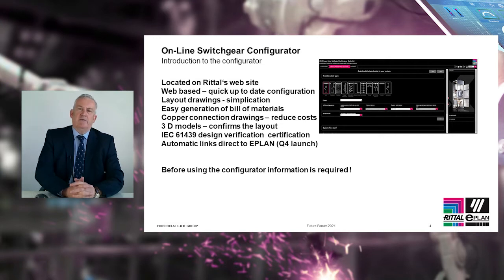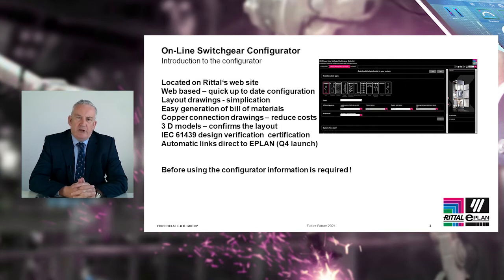Also, the 3D models are very useful to give you a sense that you're building the switchgear correctly throughout the design. And later in the year, in Q4, the configurator will jump into EPLAN automatically. That will enable you to use Pro Panel to design the switchgear to the next level, which includes the cutouts of the doors, mounting plates, and installing the switchgear, for example.